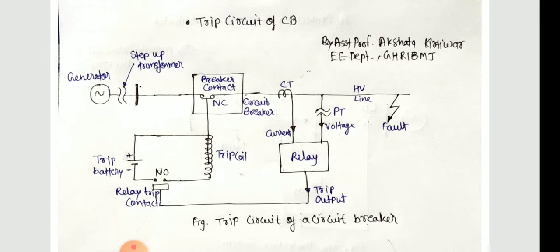So what exactly is the trip circuit of a circuit breaker? You can see the schematic of the trip circuit of a circuit breaker. The circuit breaker contacts are in a closed position by the force of spring. Energy is stored in the spring during the closing operation.